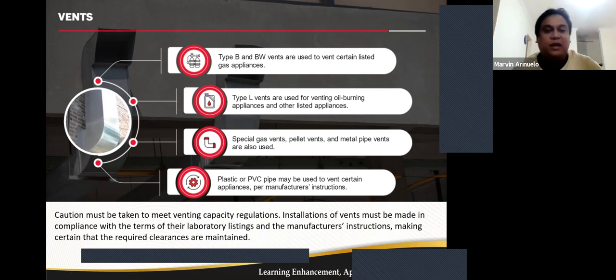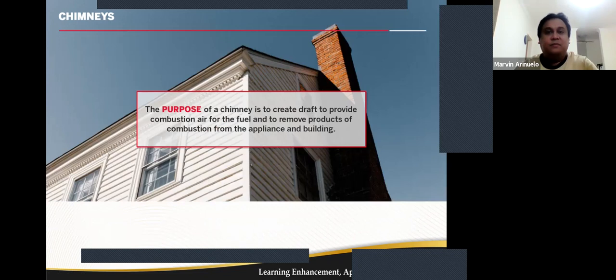Remember that caution must be taken to meet venting capacity regulations. Installation of vents must be made in compliance with the terms of laboratory listing like UL or FM and manufacturer's instructions, making certain that the required clearances are maintained.